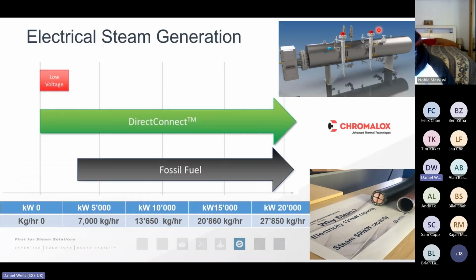But what we can do is move away from a standalone electric steam generator, electric steam boiler. And just as we can remove the gas burner from an existing boiler and replace it with a hydrogen burner, we can remove the natural gas burner and replace it with a series of electrical elements. We put those elements into the smoke tubes where those combustion gases would traditionally have passed down. In other words, we're electrifying our client's existing infrastructure. We don't necessarily have to go to the expense of a brand new replacement steam boiler. So the water treatment plant, the boiler, the safety features, the pipework, they remain the same.